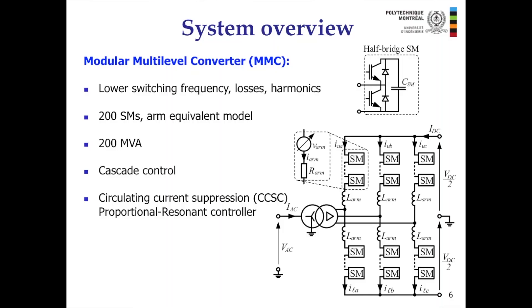This converter also uses the standard cascade control with two loops: an inner current control and an external control for power or voltage reference. Contrary to the wind farm side converter, here the current control is done in the alpha-beta frame, so it uses a proportional resonant controller. Also, for MMCs, you usually use circulating current suppression because if you just apply standard control, a second harmonic circulating current appears, so you have to take special care about it.